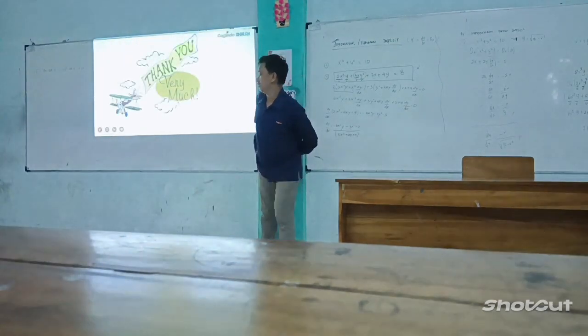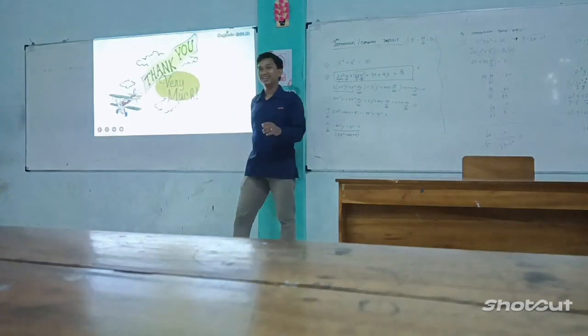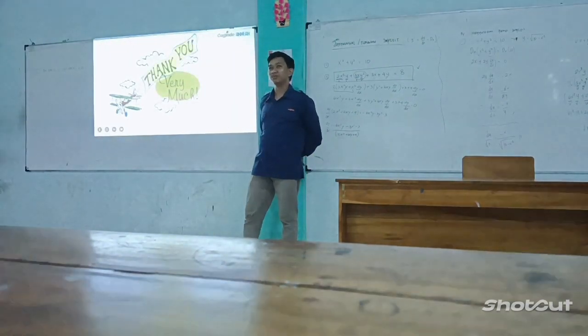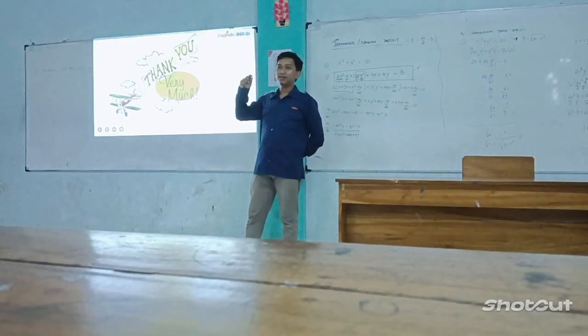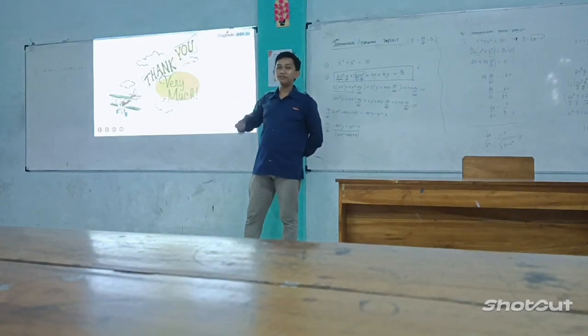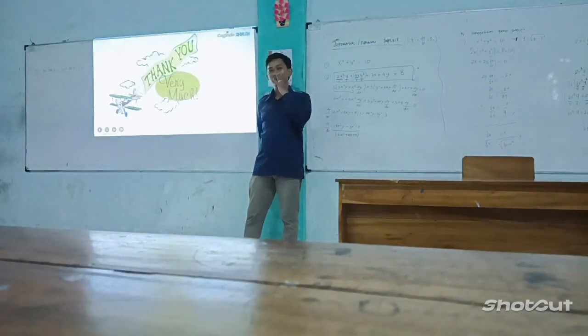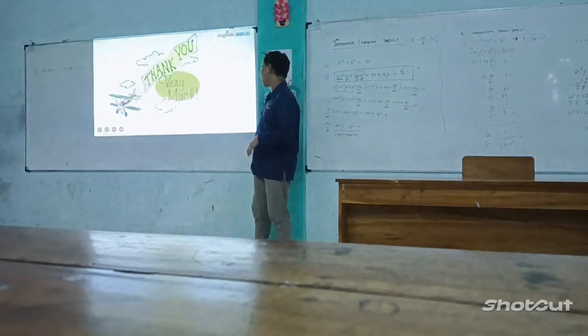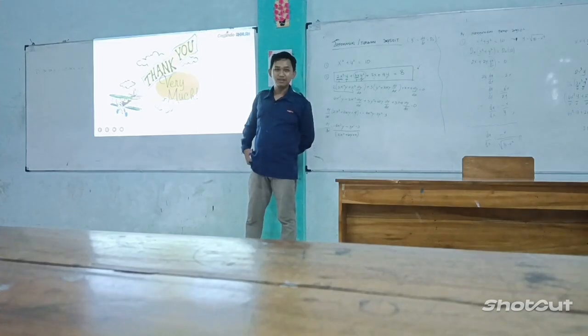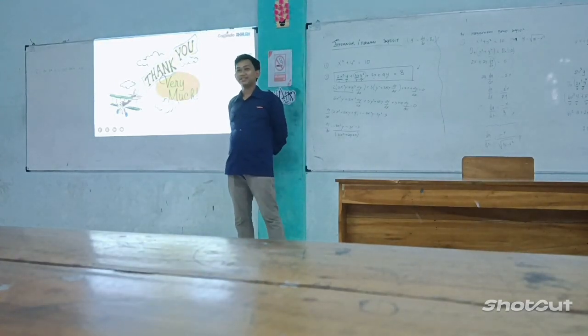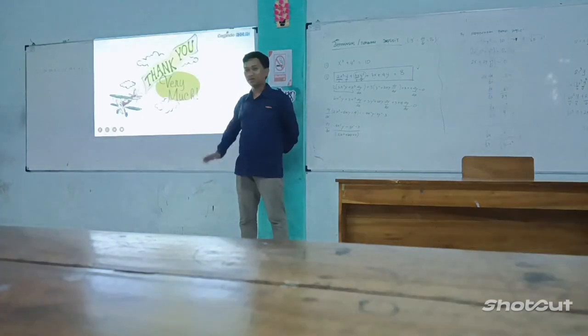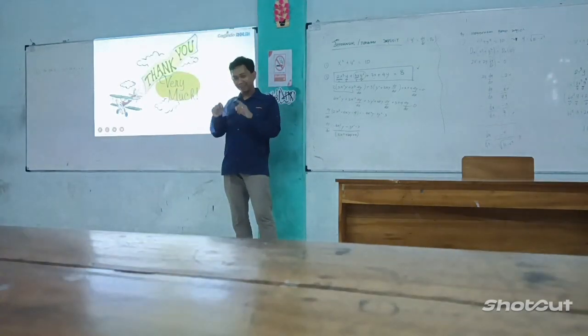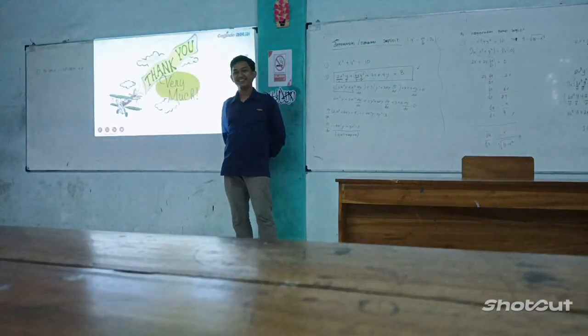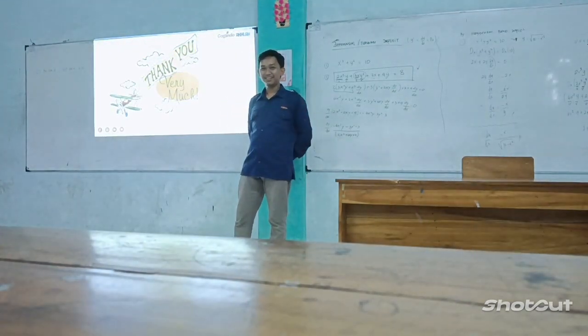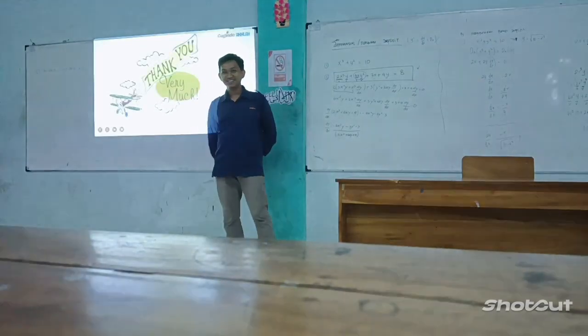So, the set point on the tanks in the water treatment system is at 90% full. Yeah, enough. Thank you. Okay, this setting is 90%, right? No, the set point is at 90% full for the tank, in automatic. Yes. Okay. Enough? Clear.